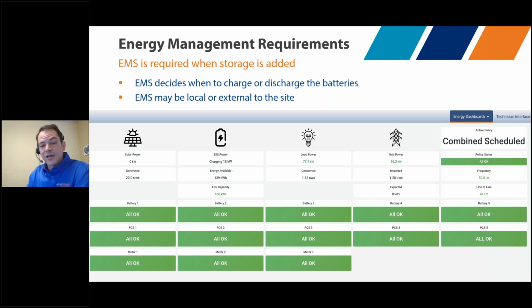In net of all that, the EMS is making the decisions as to when to charge or discharge the batteries based on what energy application is being used on this site. In this particular graphic, you can see one of our sites in the field. It's monitoring solar power, it's monitoring the battery, and you can see here it has both the energy available as well as the storage available.